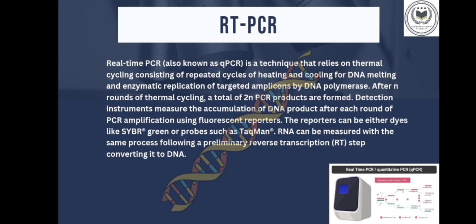Detection instruments measure the accumulation of DNA products after each round of PCR amplification using fluorescent reporters. The reporters can be either dyes like SYBR Green, or probes such as TaqMan. RNA can also be measured with the same process following a preliminary reverse transcription step that converts it into DNA.